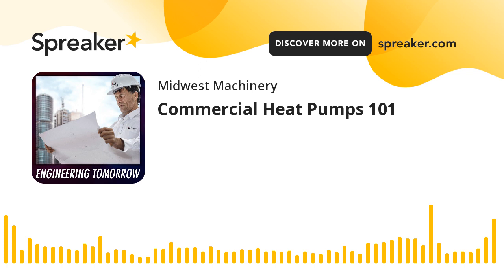So, you got a heat pump job. You're going to need water source heat pumps, obviously. Then you have to look at your plant. You're going to need loop pumps. So these are the pumps that are going to pump the water around to each individual heat pump. We typically do those duty standby, so if one goes down, the other can pick up the whole load. You're going to need cooling tower pumps for the other side of the heat exchanger to pump the water through the heat exchanger and up to your cooling tower. You're going to need that plate and frame heat exchanger.